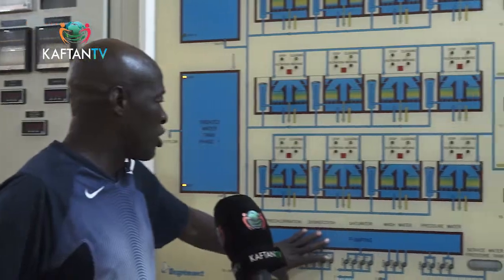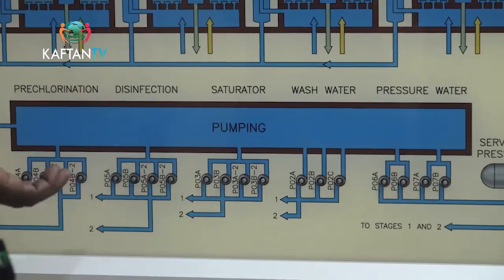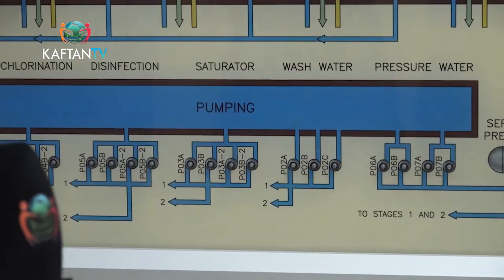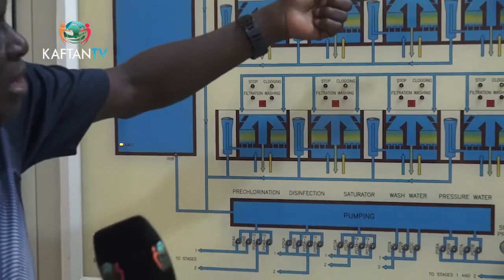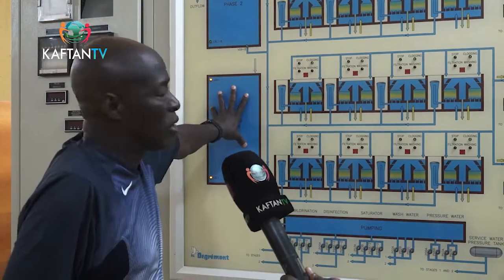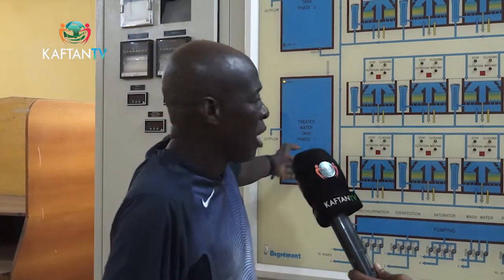We have internal pumping stations and pressure water pumps — for office use for batching tanks, batching chemicals like aluminum sulfate to make solution for the treatment process. We have a wash water pump for back-washing the sand filter bed, and a lime saturator pump. The lime comes in slurry — milky form. We mix slurry lime with lime water to produce the lime water used for post-liming. Chlorine is injected at the injection point, mixed with water to produce chlorinated water for pre-chlorination and post-chlorination.